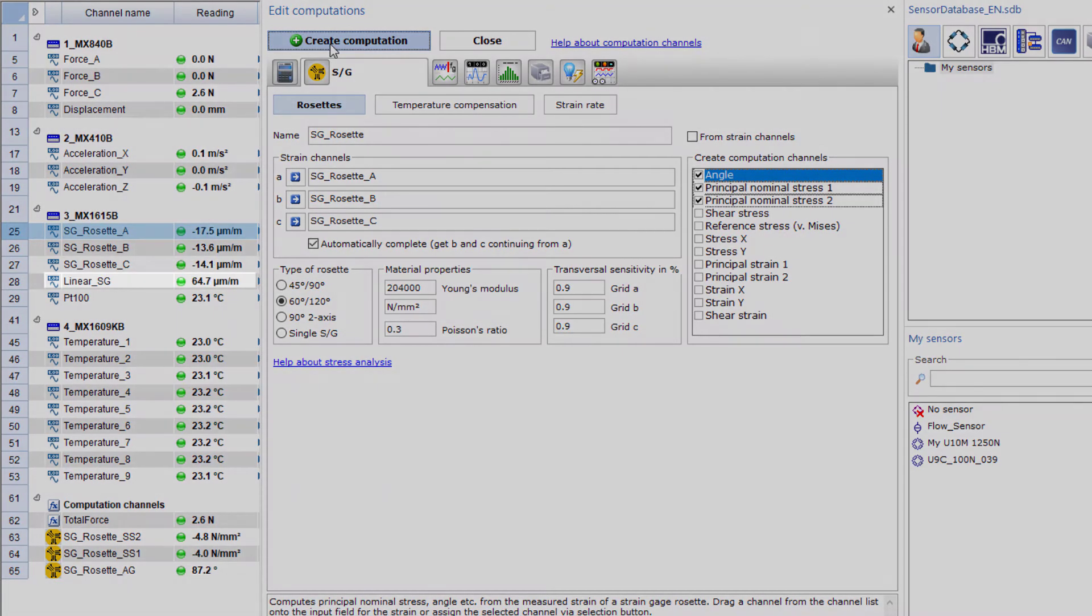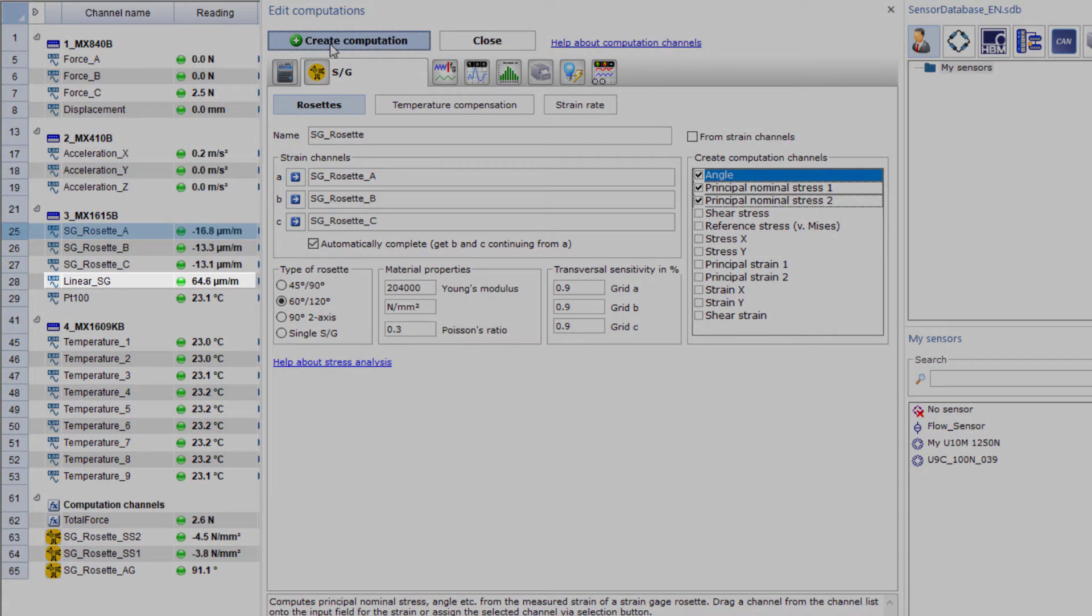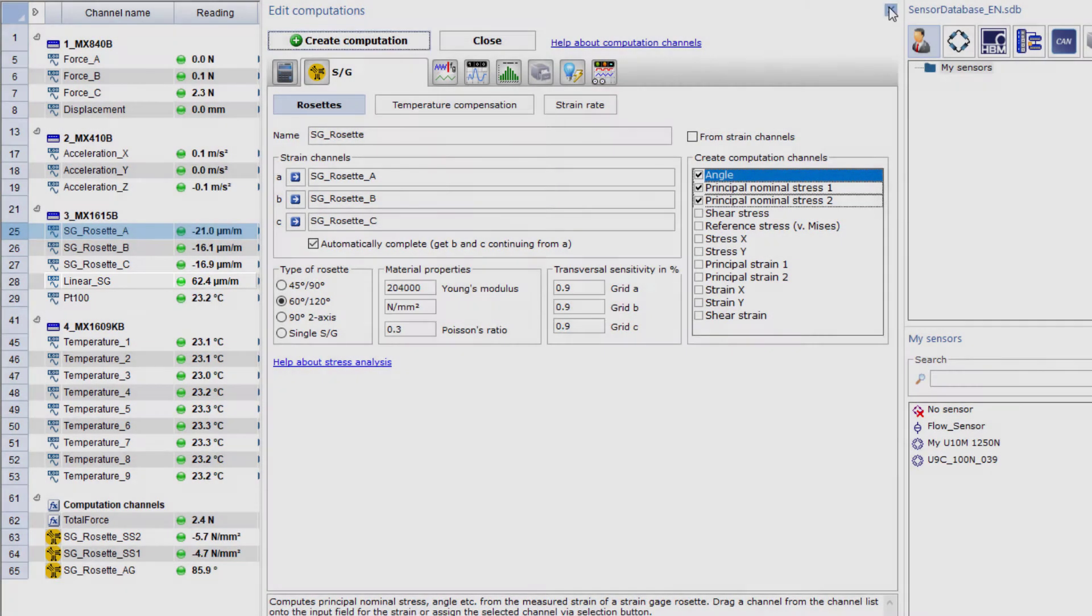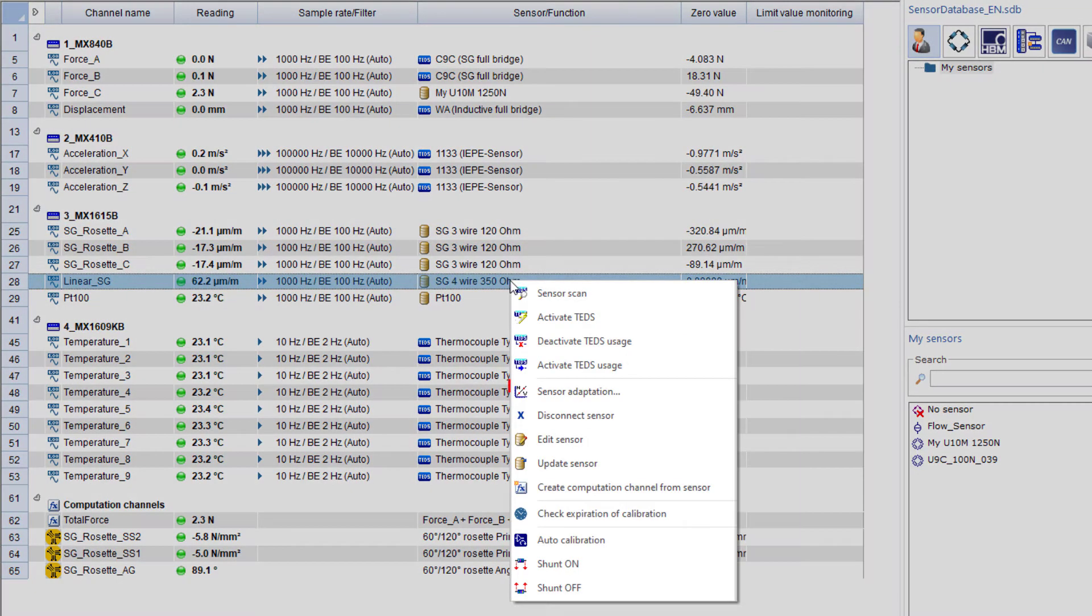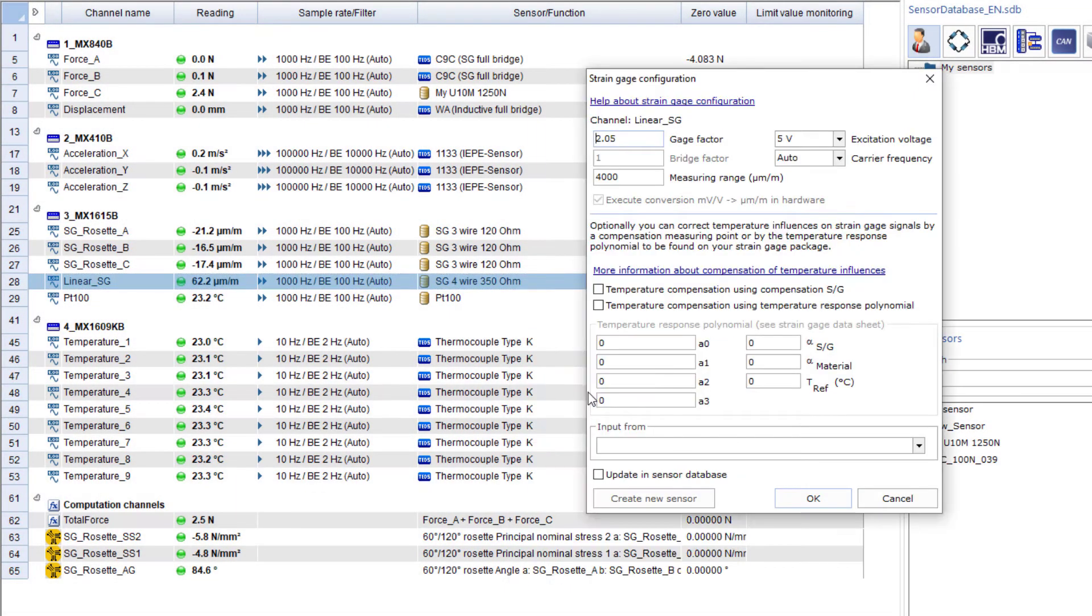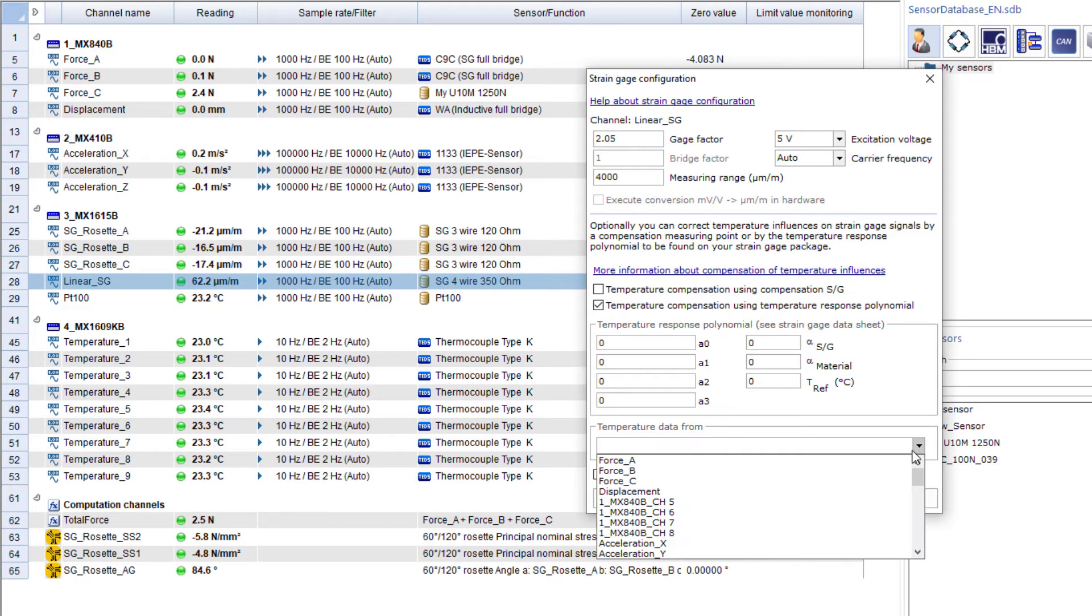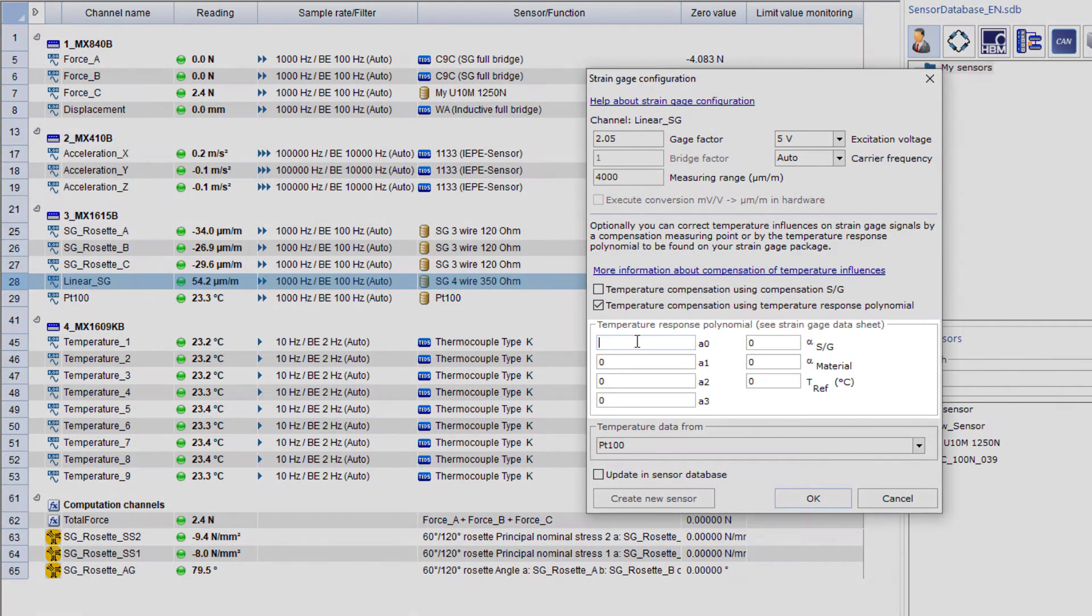With the linear strain gauge, I'll have a temperature compensation made. I could also create this calculation separately, but I'll already store it directly in the measuring channel. I'll use the PT100 for this purpose and transfer the values from the strain gauge package to the calculation.